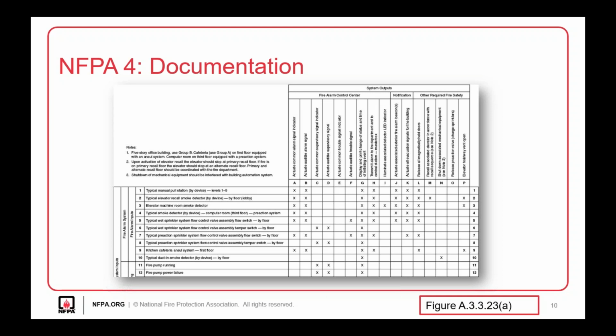Another important thing when performing a corrective action is that you need to be careful that you're only correcting the items that were not installed per the design documents. So we'll use that example of the smoke management system. Maybe you're doing the testing and you determine that some of the smoke detectors around the perimeter of the atrium aren't programmed to actuate that smoke management system. When tested, if that desired outcome is not achieved, a recommendation could be made to include those additional detectors as part of the actuation of the smoke management system.